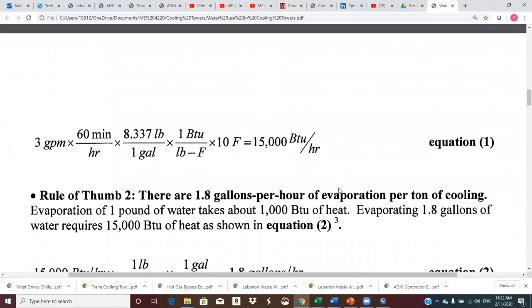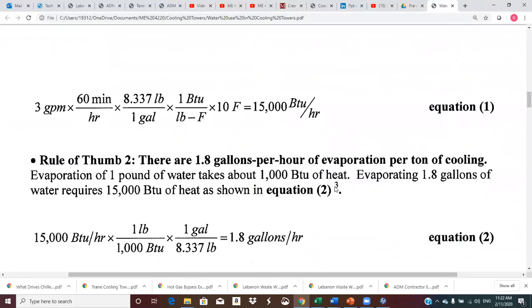Okay, so this just shows the calculation. 3 GPM times 60, that's gallons per minute, so we get the minutes out of there, 60 minutes per hour, times the weight or mass of 1 gallon of water, 8.337 here. And the specific heat is 1 BTU per pound mass per degree Fahrenheit times 10 degrees Fahrenheit. That gives the 15,000 BTUs per hour per 1 ton of refrigeration.